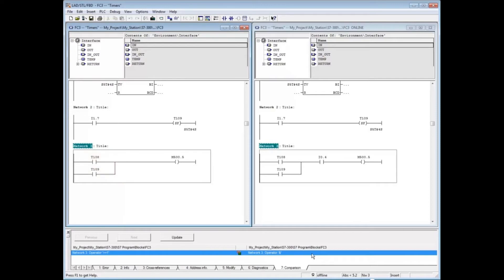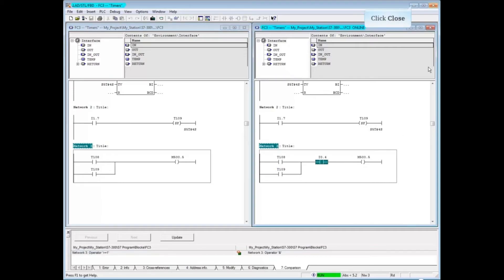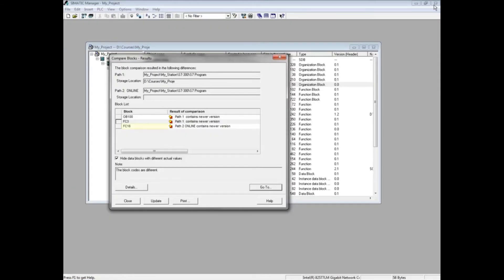In the comparison tab at the bottom of the programming editor, Network 3 in the offline block shows an operator of greater than or equal to 1, meaning the network is using OR logic. Network 3 of the online block has newly added AND logic, which is the open contact input 0.4. We would now decide which block is correct. If the offline block is correct, we would download it to the PLC. If the online block is correct, we would close the offline block and perform a save. Close the programming editor.